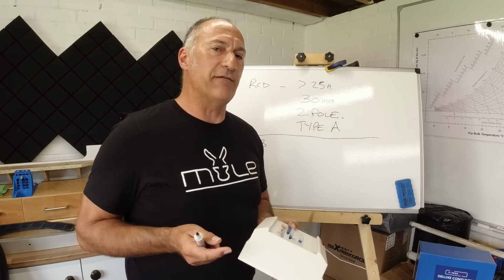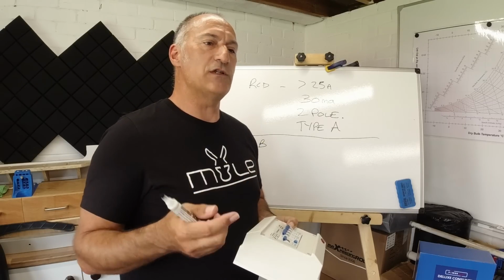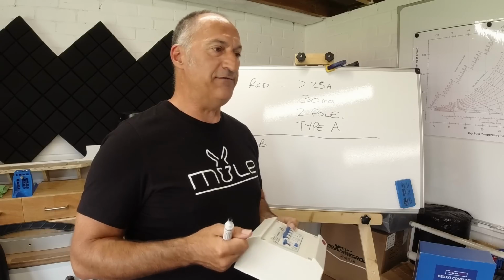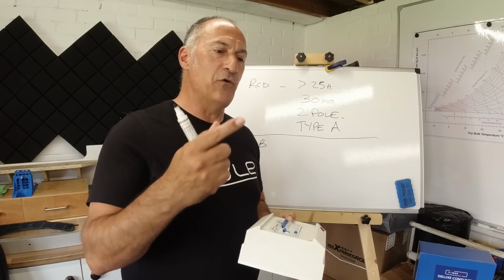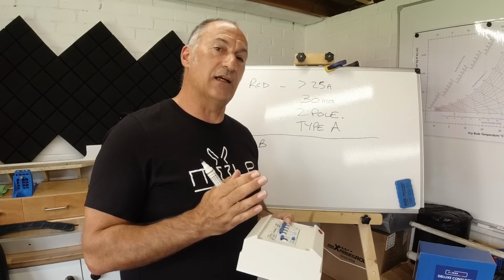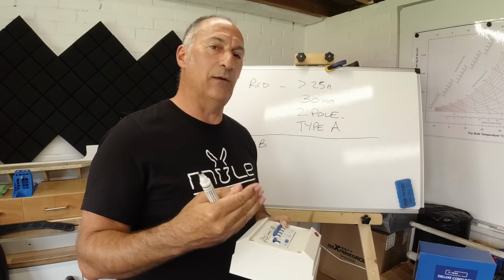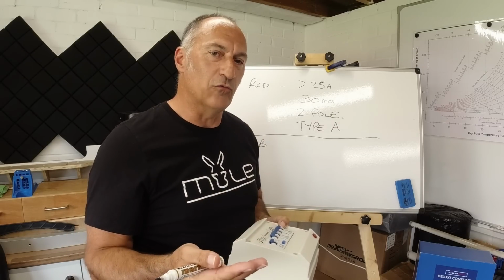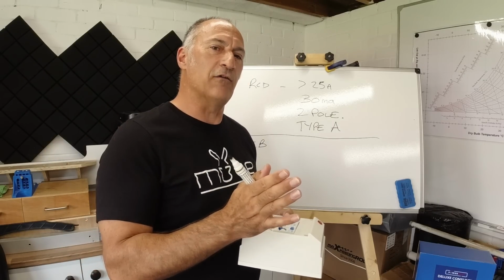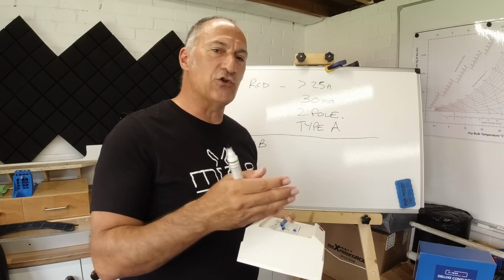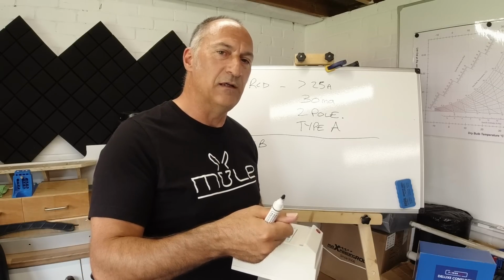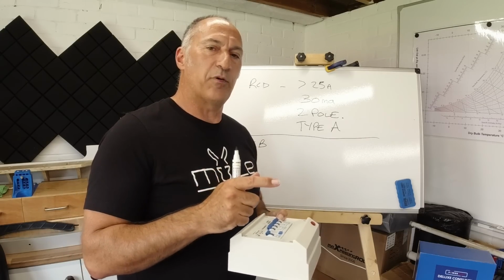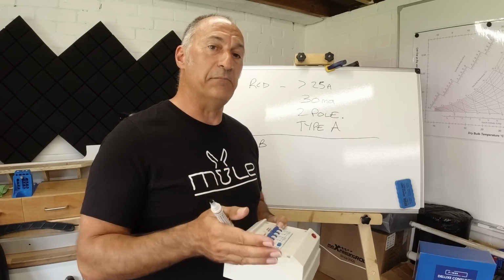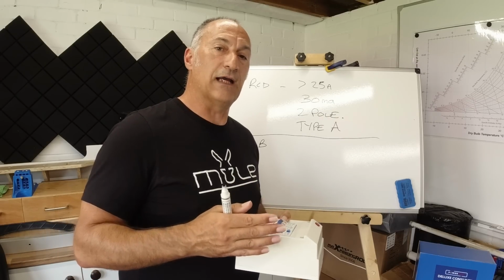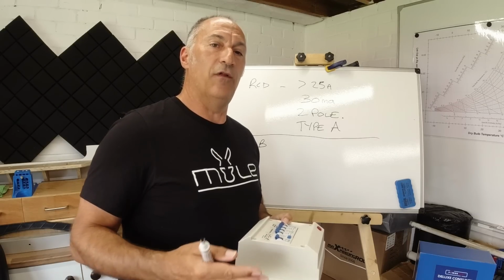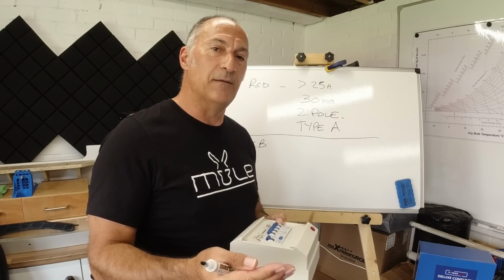Now why would they be different? Well, some motors, pumps, even hair dryers, need a high starting current to get the motor running, and then once it's running it falls back to its normal running current. They have an inrush of current, so you don't want your MCBs tripping every time you start a water pump. The better type of breaker for that circuit would be a type C, because it's got an inbuilt time delay before that MCB will trip.